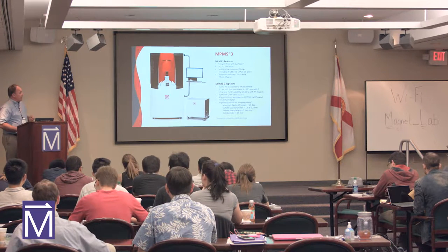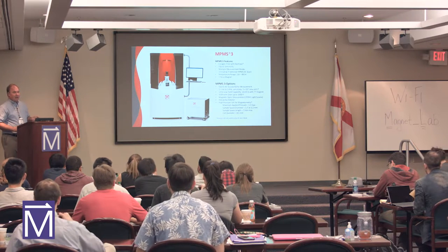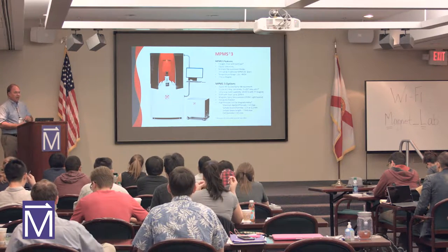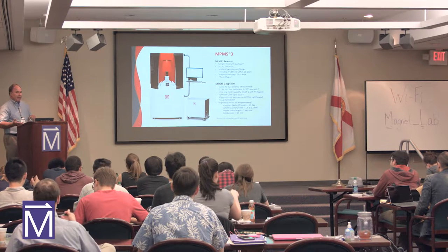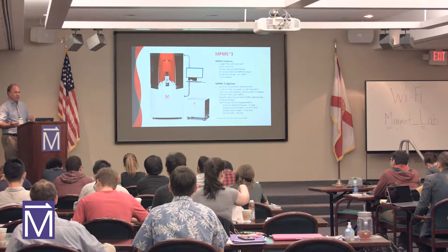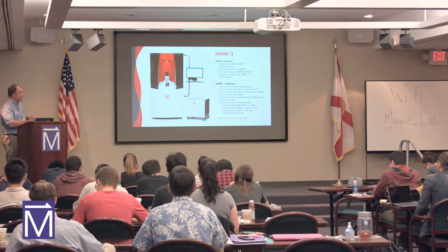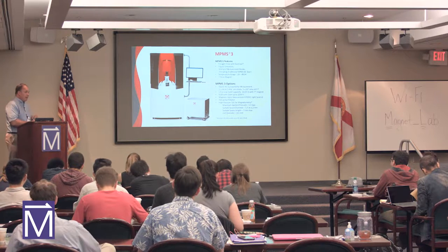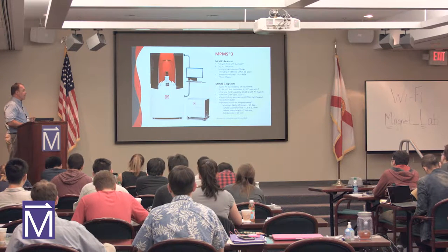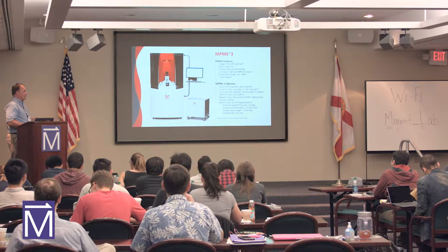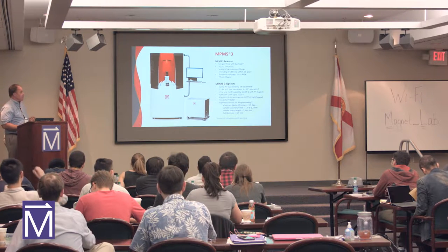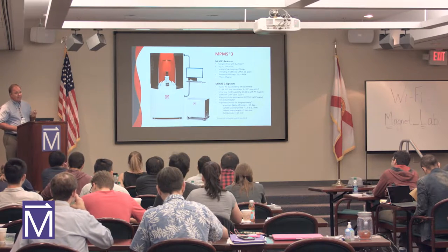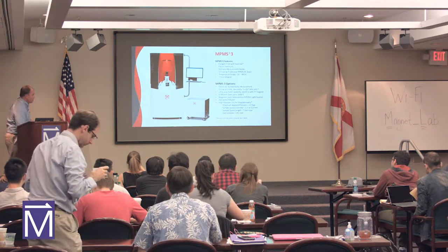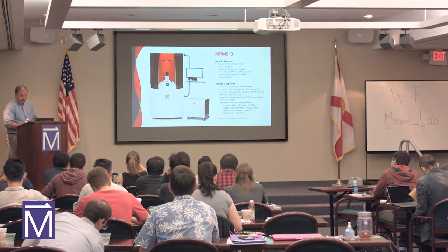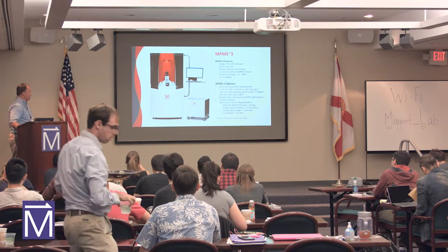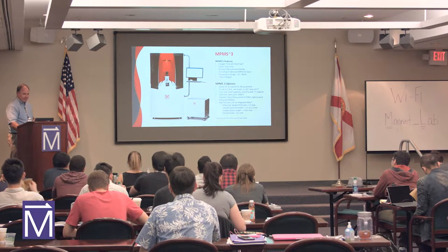We made this system cryogen free, but you might see a version in between, the XL system that's a 5 and a 7 Tesla liquid helium based system that we can also make cryogen free. So we can retrofit the liquid helium systems back into cryogen free systems. So this is the SQUID-based magnetometer system. So you can do SQUID measurements, you can do magnetometry measurements at high pressure. So we have a lot of dedicated experiments for this MPMS system. I won't talk as much about this system but there's a whole other class of experiments that you can do on the SQUID. You have a better sensitivity than the VSM.